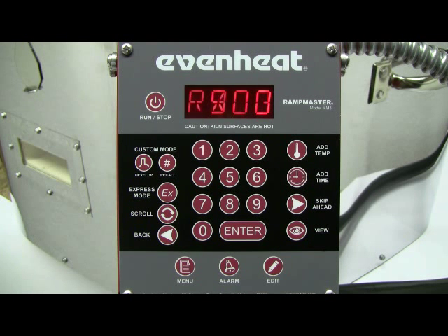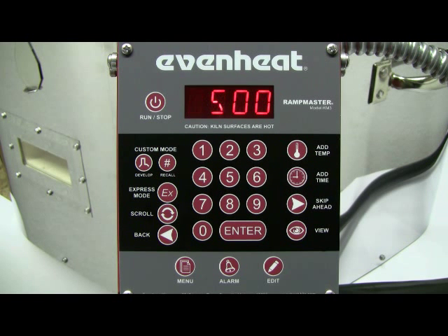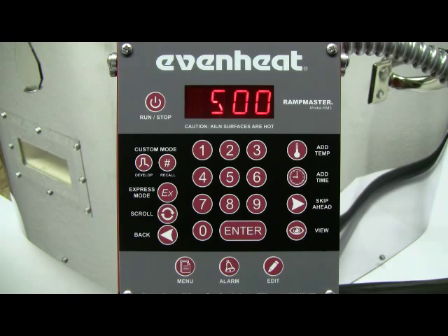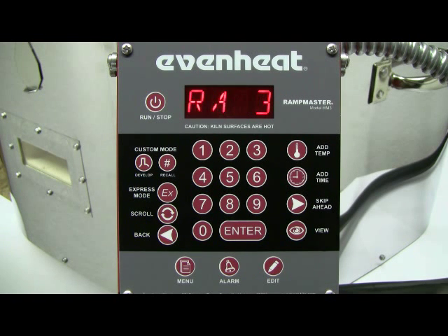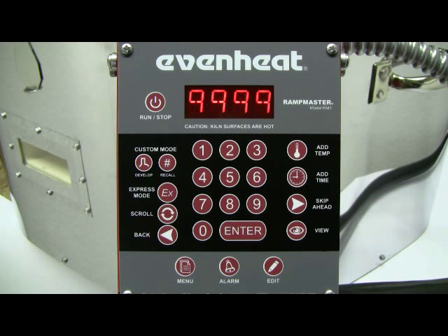The display now reads RA3. The RampMaster is asking for your temperature rate for segment 3. At this point in the firing, we're going to the anneal, so we want to go as fast as possible. To program as fast as possible into the RampMaster, use 9999. Type in 9999, then press the ENTER key to store your choice.